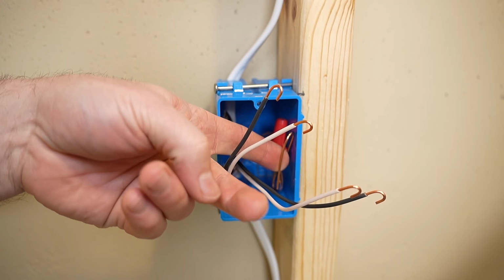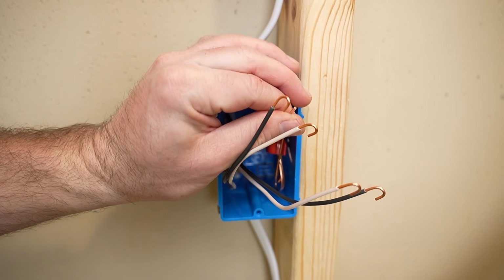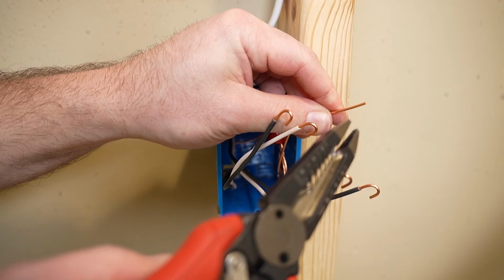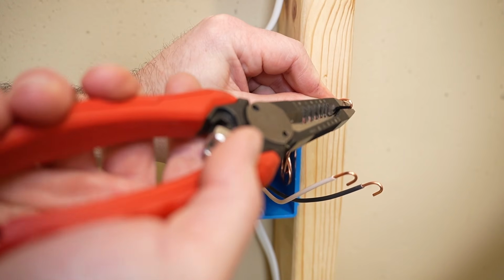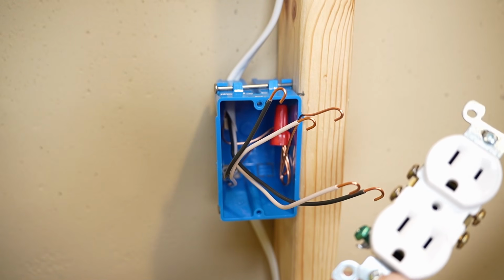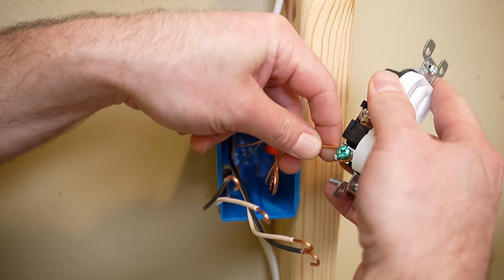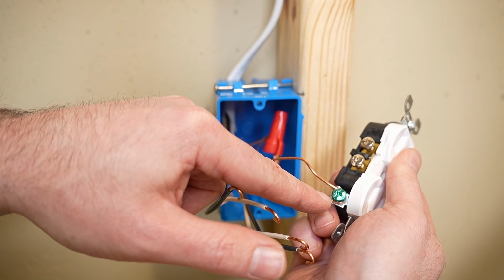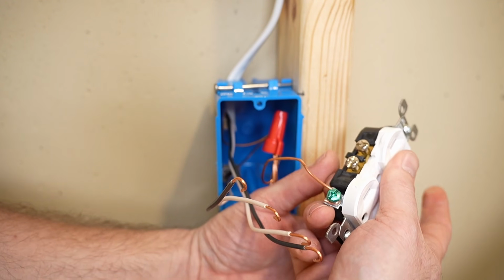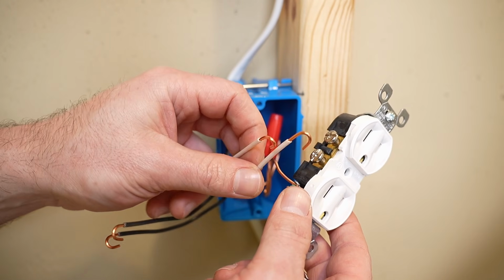Also, don't forget, we've got this ground that we did have to pigtail back here. So let's bring that out and put a loop on it as well. And now we're ready to install the receptacle. I'm gonna start with the ground. Again, we wanna make sure that wire is installed the same direction the screw is going to tighten. Then we're gonna install the neutrals.